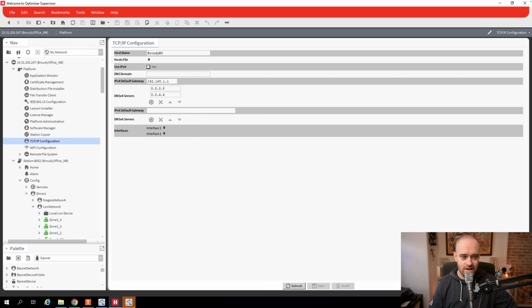So let's jump into Niagara now and get started. All right, so we are in Niagara now, and I am logged into our building JACE, which powers the whole building, and one of the first starting points, the first thing that you should be looking at and checking if you're going to use email is your TCP/IP configuration on your JACE. This is more important for a JACE than a supervisor because your supervisor likely already has this stuff done because Windows is handling it. But on the JACE side, you as the owner of the JACE, the one managing it, you have to set this portion up.